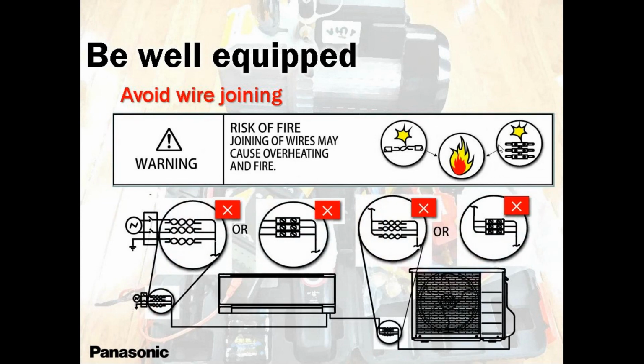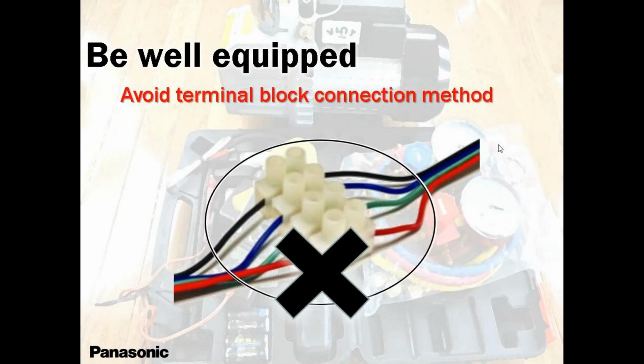Always remember, control wiring is your big enemy on a brand new startup, on a brand new installation. I get calls almost every month, at least once or twice. I'm getting an H11 code. I ask them, is it a brand new install? Yes. You have crossed the wires. No, Paul, I swear on all my gods, I have not crossed the wire. Send me a picture. They send me a picture. Right enough, they crossed the wire. Then who do they blame? Oh, my apprentice. They blame the apprentice. So no need to blame anybody, guys. Just fix it.